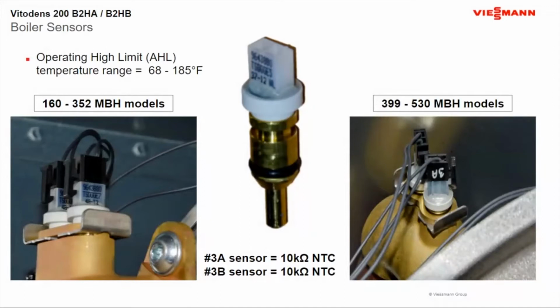With our larger boilers, from the 399, from the 160 to the 352, have two number 3 sensors, and they bounce off of each other. So if they drift about two degrees from each other, you will get a fault. If they do any type of drifting from sensor to sensor, you will get a fault between the two. They're both 10k ohm NTC resistors as well. And these are on your larger boilers as well, your 399 and your 530 models. So these wall hungs get pretty big at 530,000 BTUs.